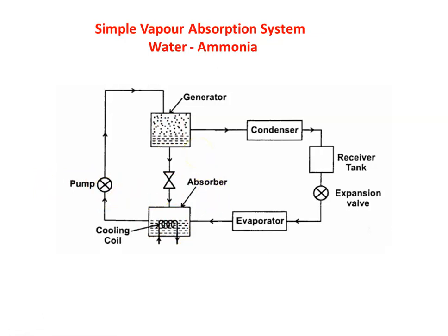How does the simple vapor absorption system work? We start from the outlet of the evaporator. The outlet of the evaporator is necessarily a vapor of refrigerant — ammonia vapor. This ammonia vapor goes to the absorber. In the absorber, we have water, and the ammonia vapor is absorbed by the water, forming an ammonia-water solution of high concentration. The vapor is leaving at higher temperature, so we have a cooling coil to reduce the temperature, keeping the solution as a highly concentrated ammonia solution.